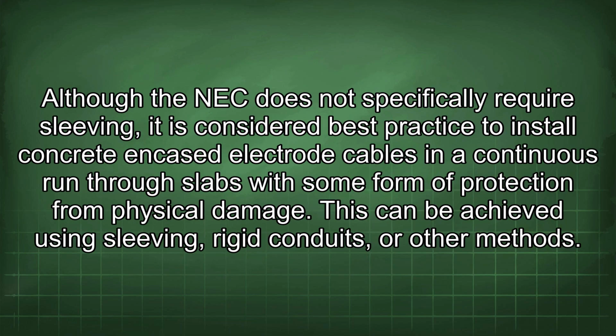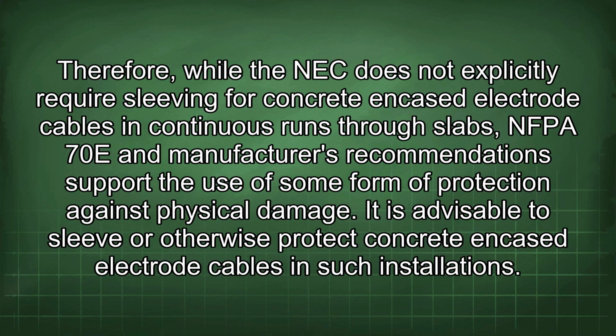Although the NEC does not specifically require sleeving, it is considered best practice to install concrete encased electrode cables in a continuous run through slabs with some form of protection from physical damage. This can be achieved using sleeving, rigid conduits, or other methods. Therefore, while the NEC does not explicitly require sleeving for concrete encased electrode cables in continuous runs through slabs, NFPA 70E and manufacturers' recommendations support the use of some form of protection against physical damage. It is advisable to sleeve or otherwise protect concrete encased electrode cables in such installations.